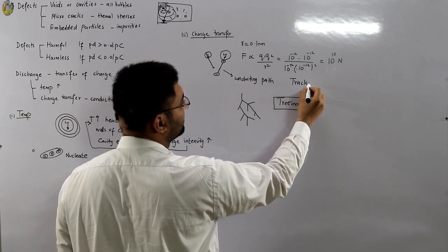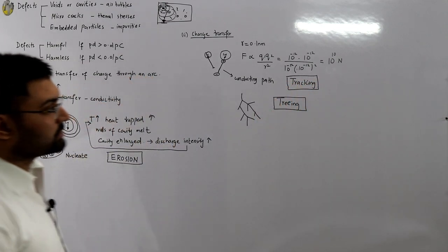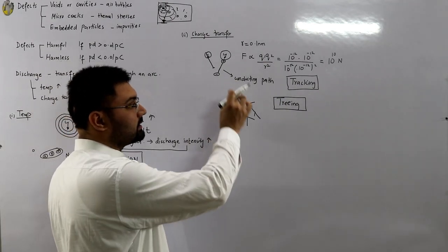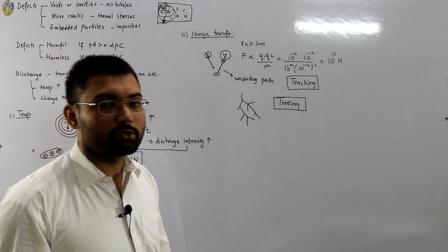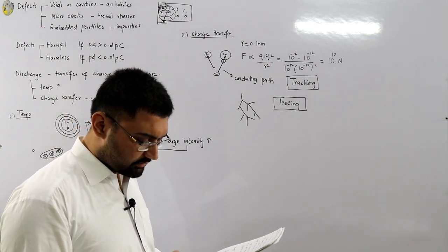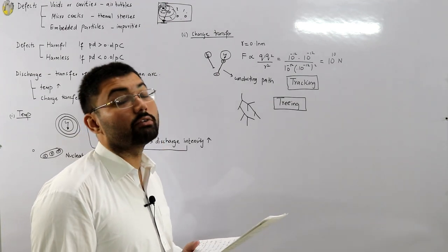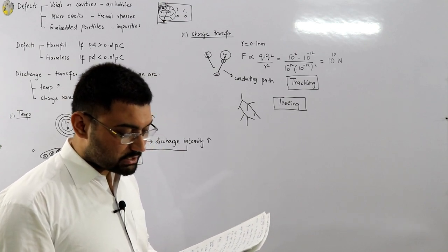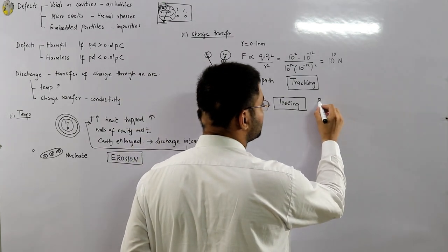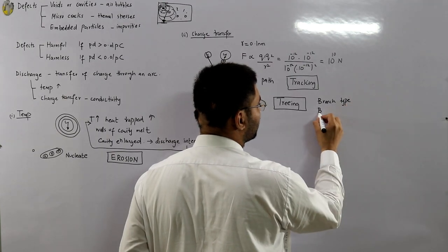Tracking is the formation of a conductive path by the attraction of oppositely formed charges. In treeing, fine channels branch out like a tree trunk with branches, due to the non-uniformity of the dielectric material. These branches spread within the dielectric and can be branch-type or bush-type trees.